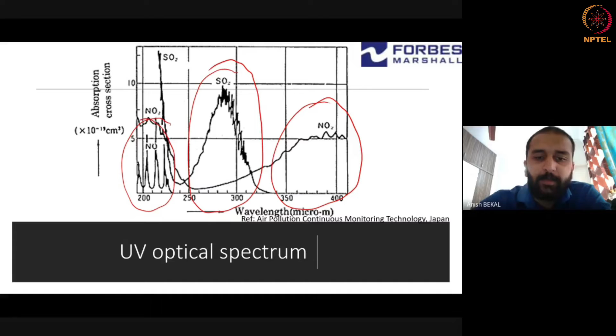Okay. So let's give a brief idea of a UV-based optical spectrum in order to solve our present problem, which is to basically measure SOx and NOx and things like that. I showed you the specs that we are talking about, right? So in order to solve that problem, how do we go about it? One way of doing that is UV spectroscopy. There are available databases which tell you what the spectrum of each of these gases is. This particular graph shows the absorption cross section, which can of course be converted into the absorption coefficient, with respect to wavelength in a UV spectral region. So if you look at this, NO2 has a pretty good absorption spectra between 350 to 400 nanometers. SO2 has a good spectra between 250 to 300, and NO has a good spectra between 200 to 250.